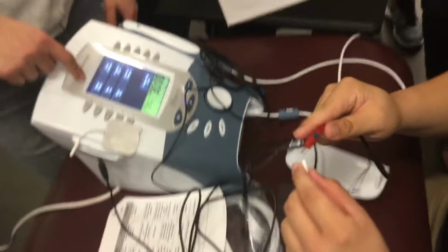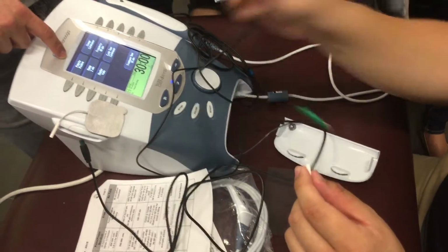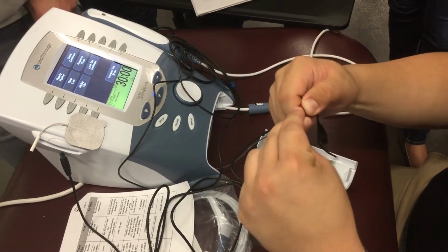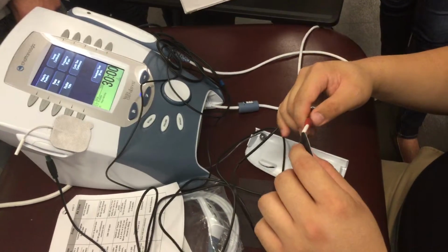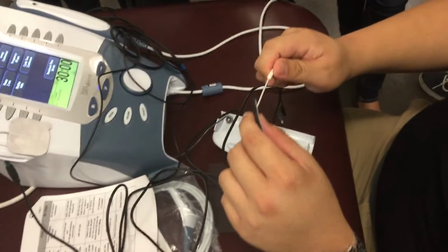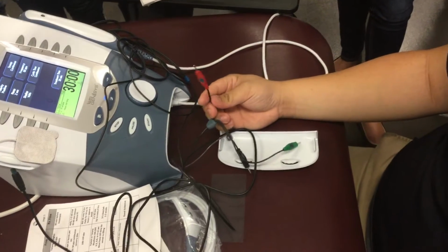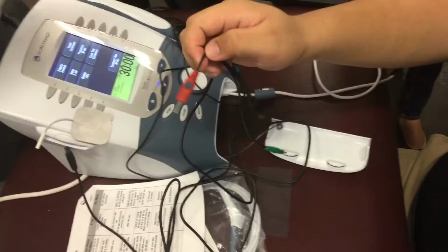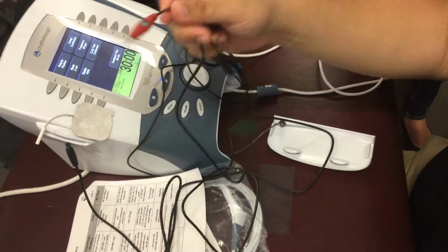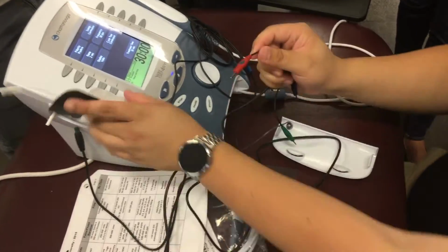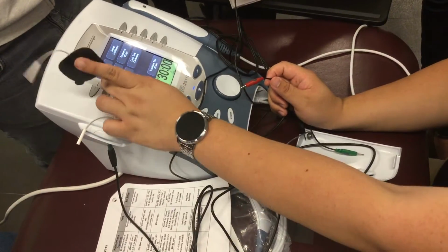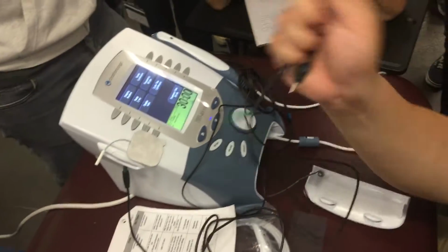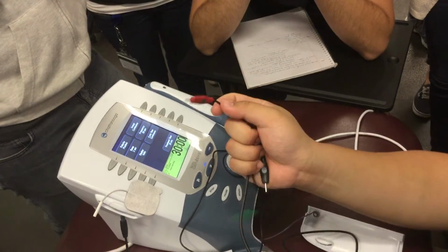What if we had put polarity negative? Use red. Red changes. Red is this polarity. Red is the good one. Always use it. So if you're doing wound, polarity positive, red into the electrode over the wound. If you're doing edema, negative. Let me just repeat it one more time. If you're using HVPC, you're going to change the polarity on the machine, positive or negative. That determines the polarity of this red. It's not the same as ionto.